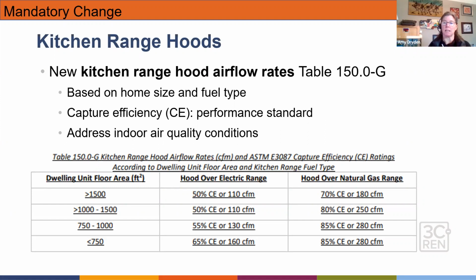So you can see there's an increased CFM requirement for gas over electric ranges. In addition, there's this metric called capture efficiency. It's a performance standard, the ASTM, that was developed to evaluate, as it says, the capture efficiency: how that hood is structured, how far it comes over the front burners, what that kind of sump is, to be able to draw those pollutants into the range hood and exhaust it out of the home.